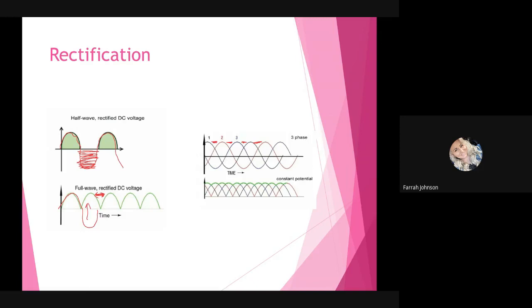Then when they took the three-phase power and rectified it, once again, they took those waveforms that were going to be down below the middle line, which were negative. They flipped them up, upside down, and now you have very minimal gaps in between each waveform. So now your incoming current is going to be near constant because those gaps have been eliminated. So that is the whole purpose of rectification: we want to utilize those negative half cycles. We want to flip them up on the positive side so that we can get a more average high potential across our tube.